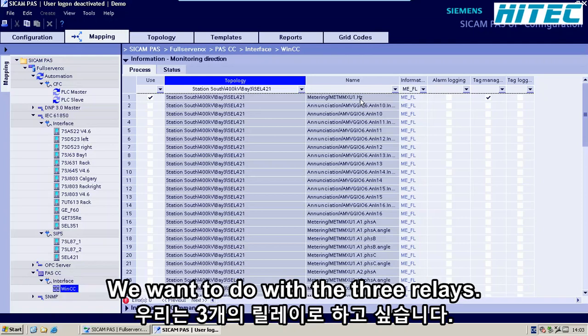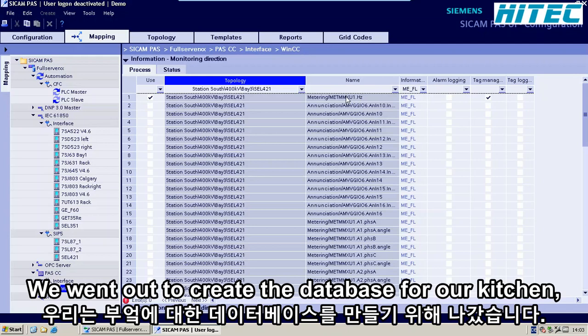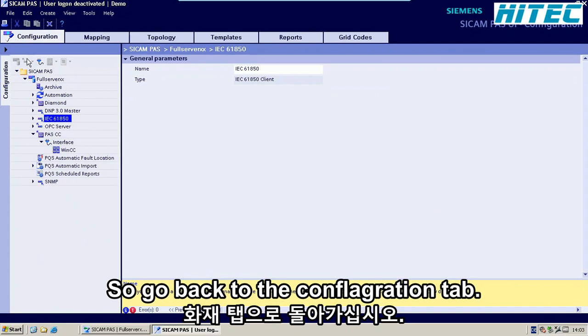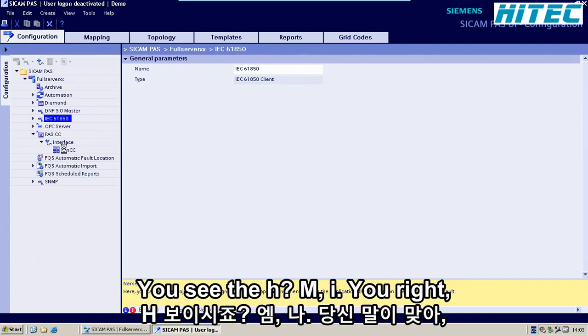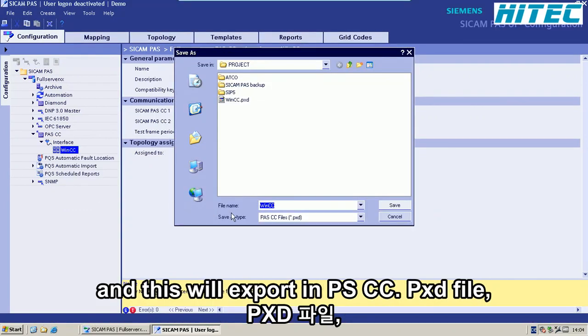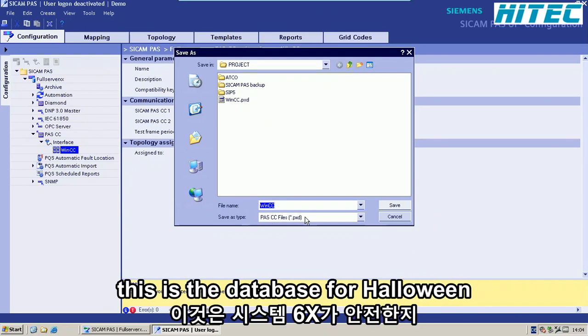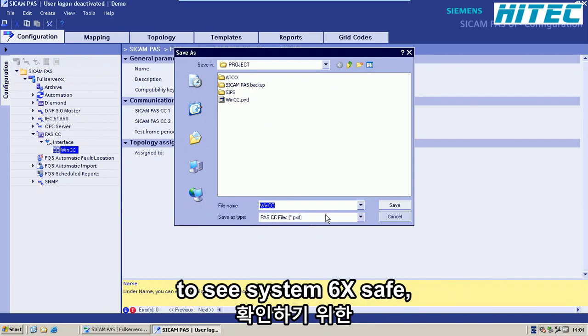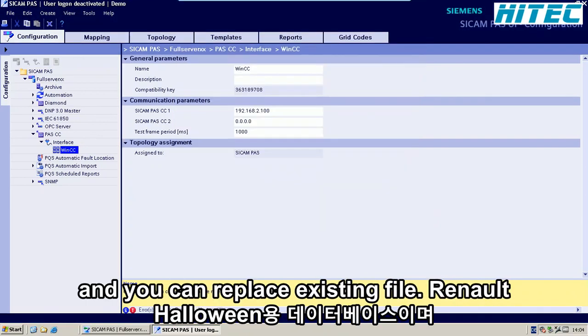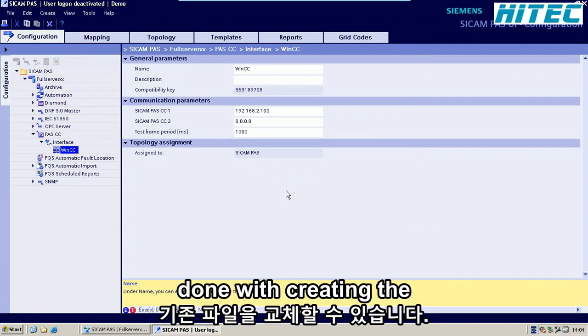So now we're done with all the information we want to do with the three relays. We want to create the database for our HMI system. So go back to the configuration tab, go down where you see the HMI, right-click on the symbol and say export. This will export a PAS CC .pxd file — this is the database for our WinCC system. Click save and you can replace the existing file. We're now done with creating the database.